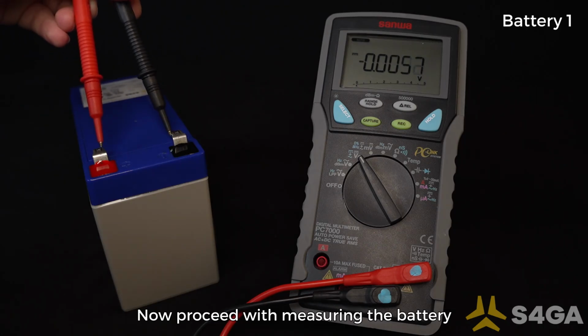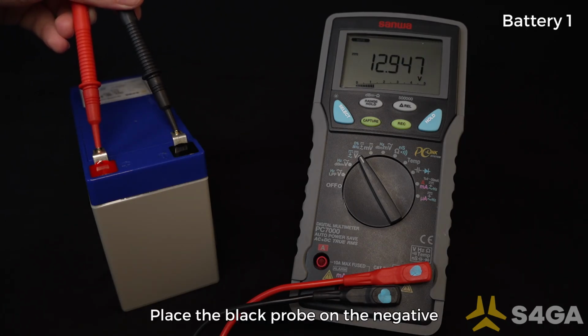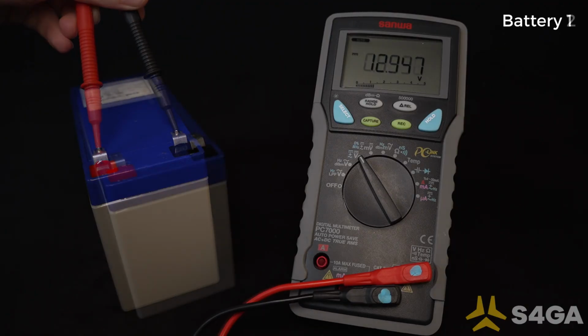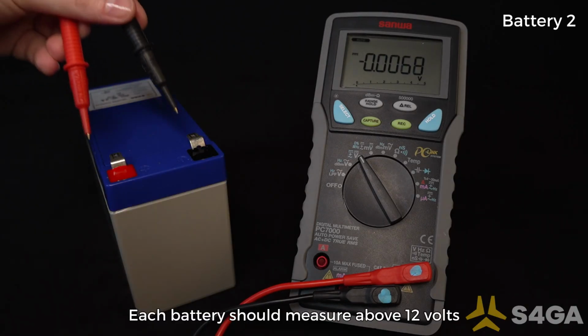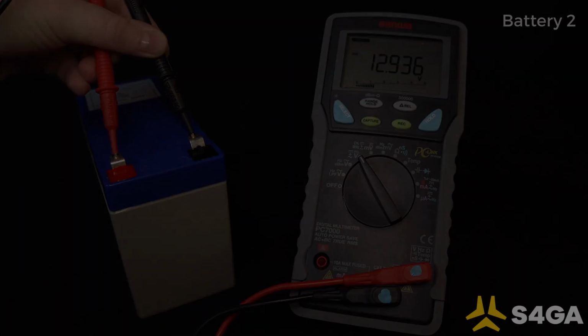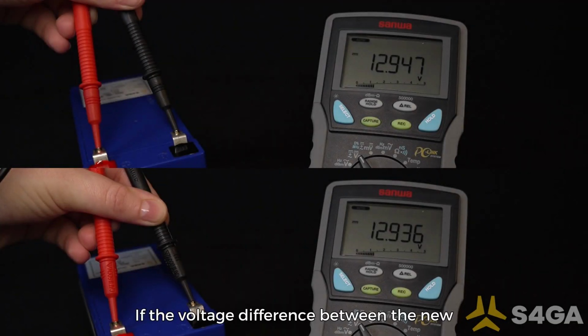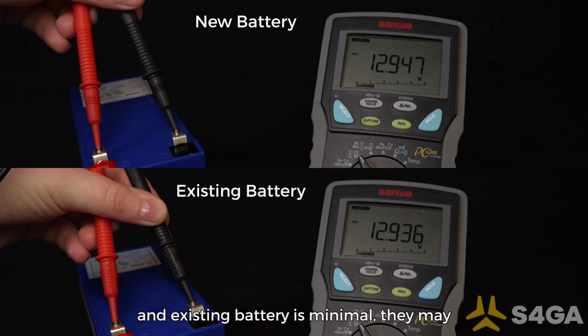Now proceed with measuring the battery voltage. Place the black probe on the negative terminal and the red on the positive terminal. Each battery should measure above 12 volts before installation. If the voltage difference between the new and existing battery is minimal, they may be installed together. In practice, simultaneous failure of both batteries is unlikely. Therefore, replacing only one battery may be sufficient when the voltage difference is small.